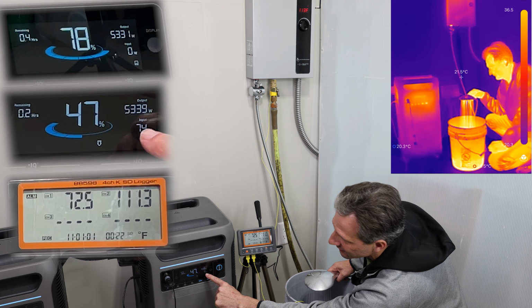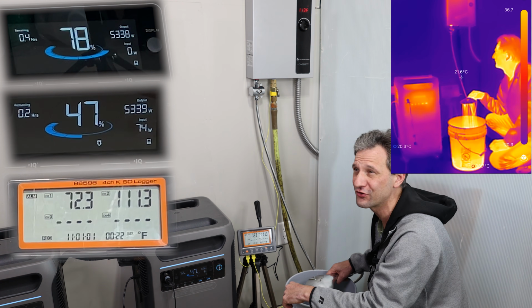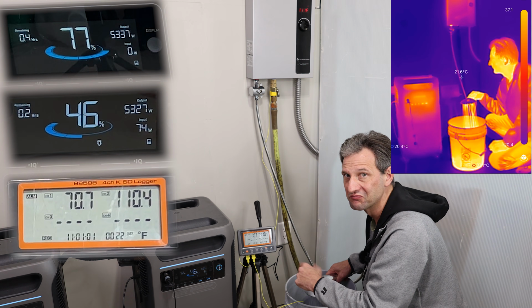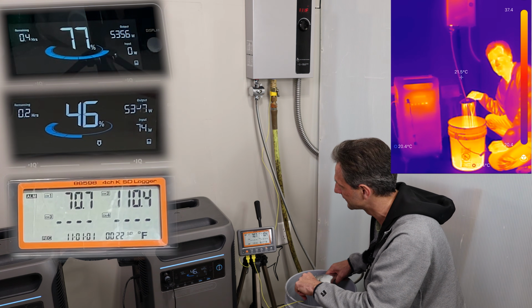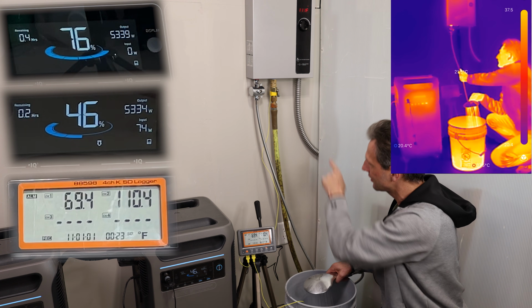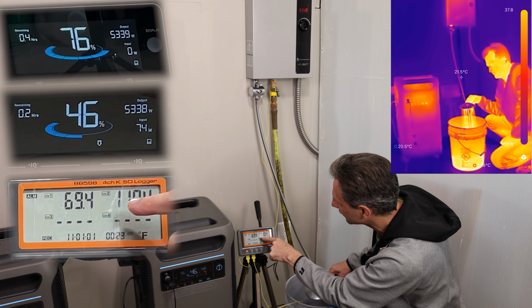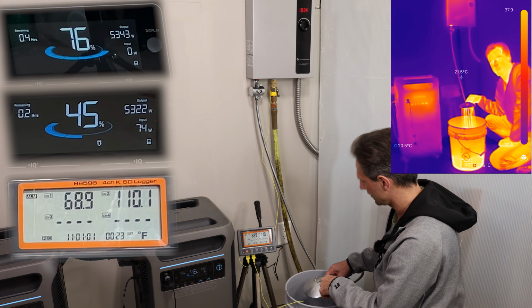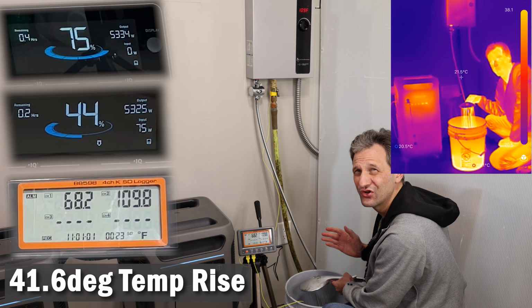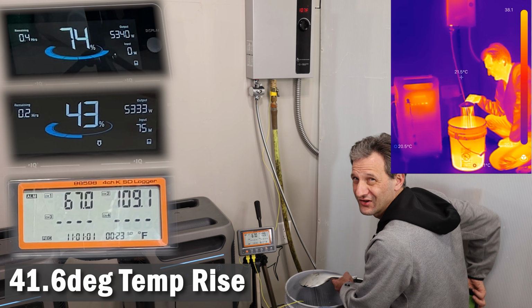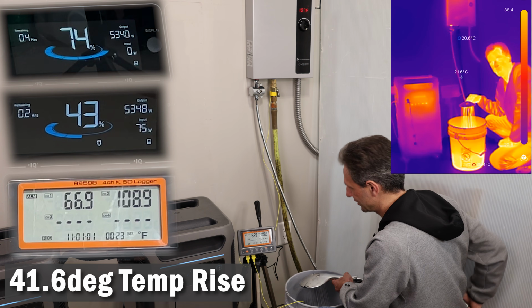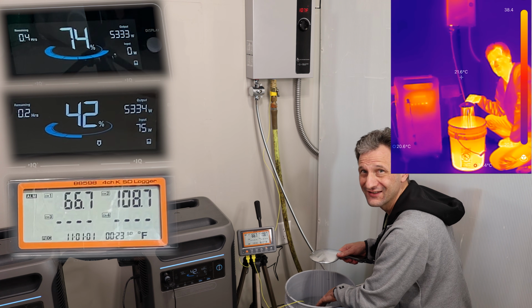We're pulling 5,300 watts out of each inverter, pushing these things pretty hard, and yet I don't even hear the fans coming on yet. Now, we were getting 113, and it's come down a little, and that's because the water coming in is getting a little colder. I bet you it's actually colder than that. It says it can do a 35 degree temperature rise. It's actually a 42 degree temperature change. Woo! That is hot.